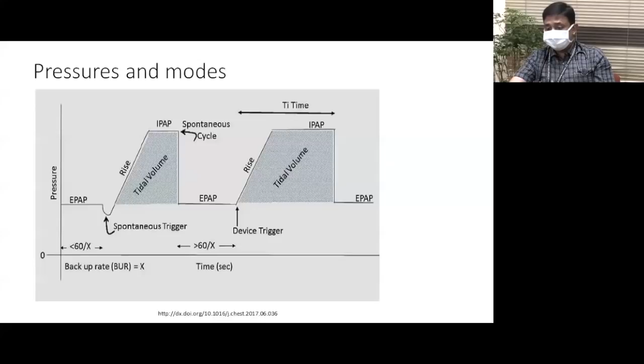Now, during inspiration, if it is a triggered breath, the pressure probably drops slightly. If it is a machine-delivered breath, there is no trigger, as we see prior to the second box. Then there is a rise, the steepness of which is determined by the ramp setting. That is how fast you reach the inspiratory positive airway pressure, which is the topmost pressure one would reach during the inspiratory cycle. And the difference between the inspiratory positive airway pressure and the expiratory positive airway pressure is the pressure support.